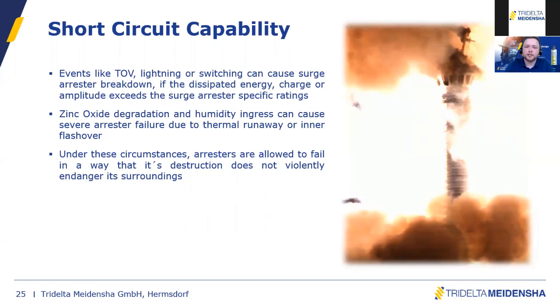In that case, the surge arrester can break down, and that's the case when we talk about a so-called short circuit. So the surge arrester will go into a short circuit mode. The resistance of the surge arrester goes down, so all the energy of the connected line can flow through the surge arrester.